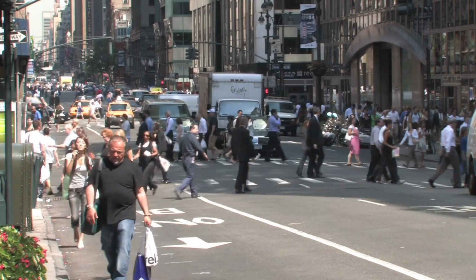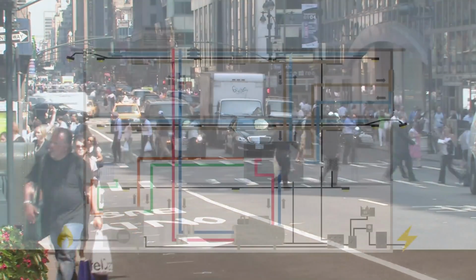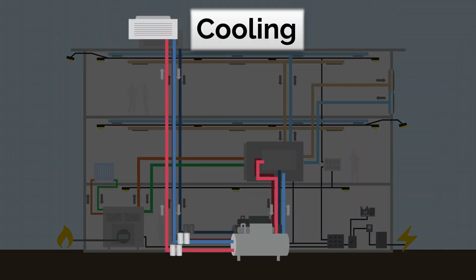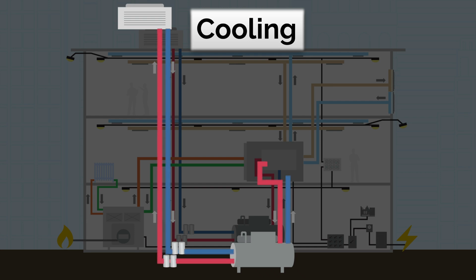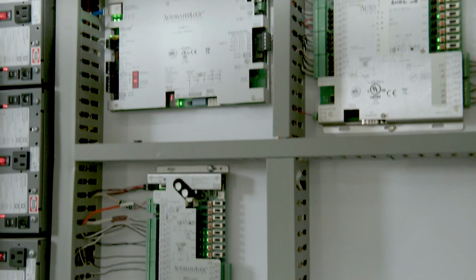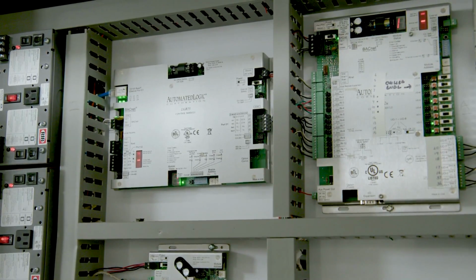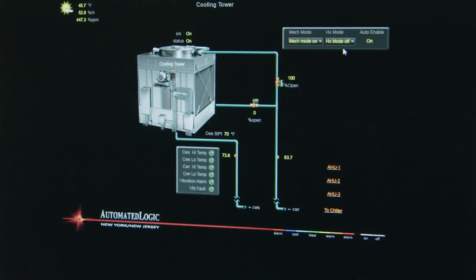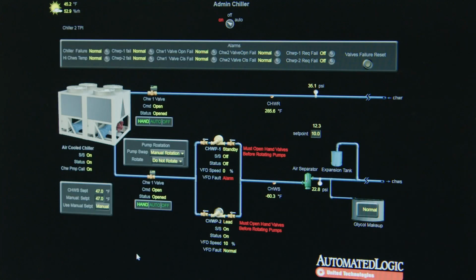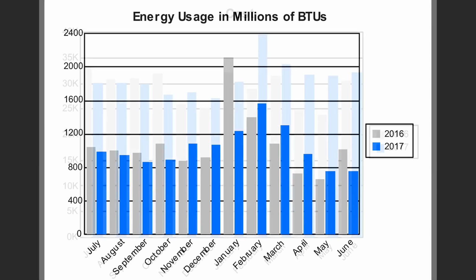We provide cooling during the warmer months, and to achieve that, we use a chiller system as well as the cooling tower and package units that provide cooling throughout the building. To reduce energy consumption in the building, we use the control system to optimize the cooling by scheduling the systems to help reduce energy usage and electricity usage in the building. Cooling uses electricity. Electricity is expensive, and this is a good place to save on costs.